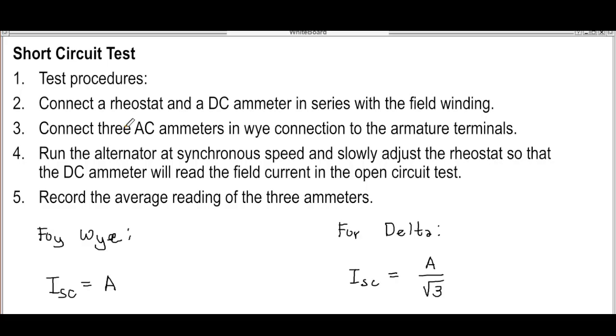Short circuit test is used to determine the short circuit current of our generator. No? So connect the rheostat and a DC ammeter. Then connect 3 ammeters in Y connection, so naka Y, tapos para natin yung ating generator, tapos i-record yung average reading ng ating ammeter. For Y, equal lang po yung reading ng ammeter sa short circuit current. For delta, yung ammeter, i-divide mo ng square root of 3 to get the short circuit current.